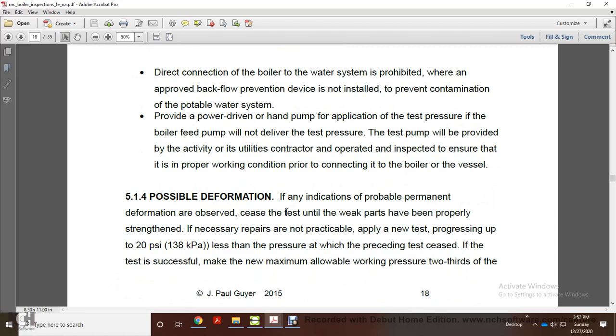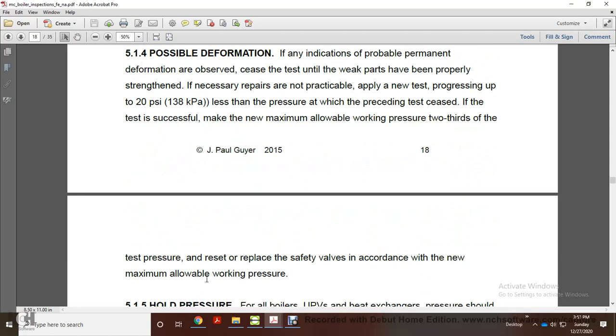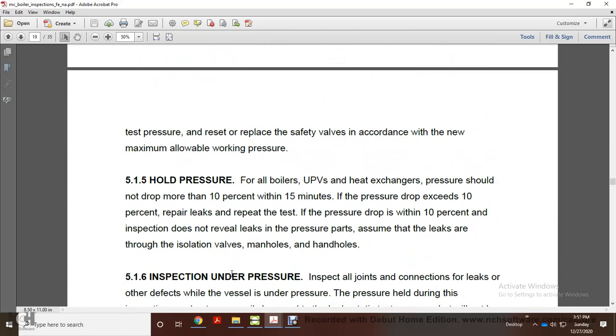5.14 Possible deformation. If indications of possible deformation are observed during the test, the weak parts of the vessel must be properly strengthened. If the necessary repair is not practical, apply a new test progressing to 20 psi less than the pressure at which the previous test ceased. If the test is successful, the maximum allowable working pressure is 2/3 of the test pressure, and the safety valve must be reset or replaced in accordance with the new maximum allowable working pressure.